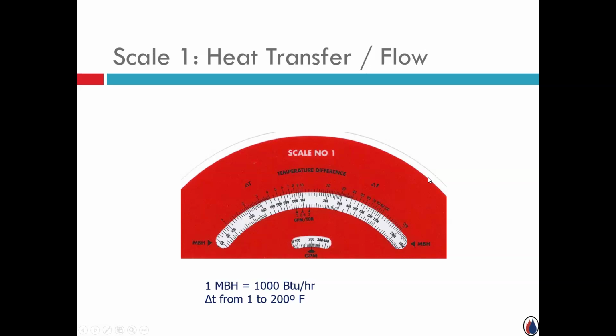All it is doing is taking the little math formula we looked at briefly last week, and he just plugged it in. And to make the scale work, that's one of the reasons why he used 1 MBH to represent 1,000 BTUs an hour. The delta T scale is pretty extreme, from 1 degree all the way up to 200. That's pretty extreme for the industry, but there are some crazy applications where you might get relatively high delta T's. When we get into primary-secondary pumping and some design examples, sometimes you'll see 60, 80, 100 degree delta T's. So it does come into play, not an everyday thing, but it does happen.